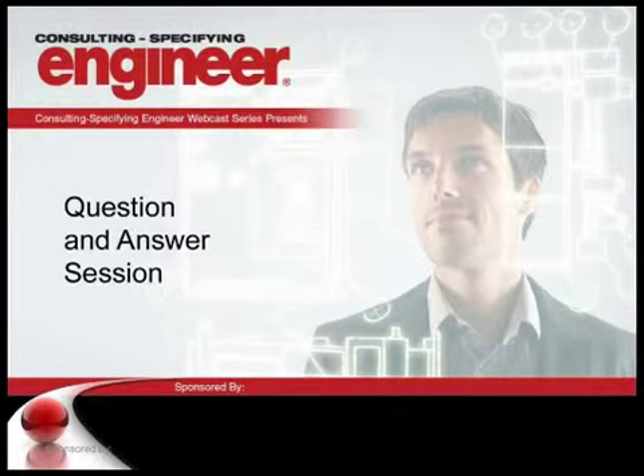Okay. Well, NFPA, NEC 517.30 actually deals with how many transfer switches you have. If you have a load for a building, let's say a small hospital or a small surgery center, and you have less than 150 kVA worth of essential system loads, you can do one transfer switch. It doesn't say that life safety is limited to 150 kVA, but that if you have low enough load for the overall essential system, you can just do one transfer switch.